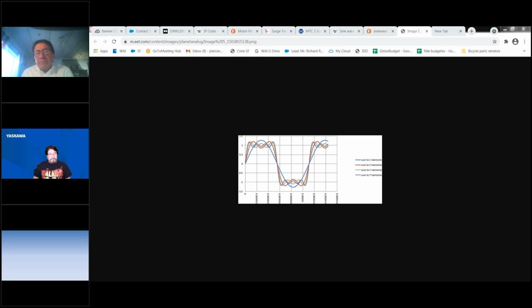You put a sine wave filter on the output of a VFD, it's not only a high pass filter, it's also a low pass filter. So it's kind of a double filter, and it's expensive. It's about the cost of the VFD, so you've doubled the purchase price. I'm going to disagree a little bit with my colleague on the installation costs. I'm going to say that the installation costs are probably more than double because of the extra piping, the weight of this thing, the fact that you've got to put it into an additional space, so you're taking up more real estate. But the real cost of these filters, quite frankly, is the efficiency. Craig, what do you say, 2 to 3% tag on the energy bill? Oh, at least 3% at minimum.